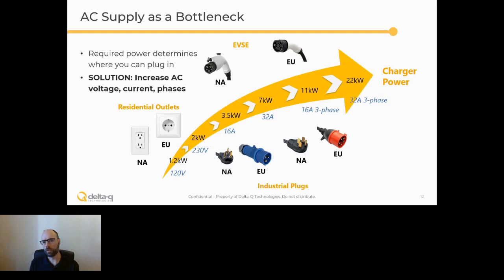So you'll often see chargers that are 3.3 kilowatt, 6.6 kilowatt, and 10 kilowatt if they're talking about the output ratings. Marketing folks like to talk about the input ratings, which are a little bit higher: 3.6, 7.2, and 11. But those all basically mean drawing 16 amps or 32 amps from a 230 volt line for 3.3 or 6.6 kilowatts. In some cases, drawing 48 amps from a 60 amp breaker on a 230 volt single phase line to get 10 kilowatts.